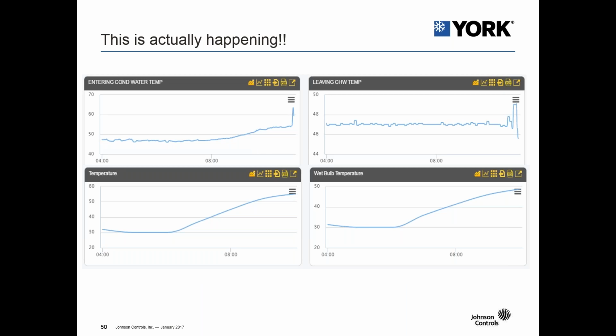So here's just a quick screenshot of our dashboard that we have for connected chiller services, where we're able to monitor chiller performance and chiller operation if the client chooses to request that service. So here's an installation we have at a pharmaceutical research lab in the Northeast region of the United States, and you can see we have entering condenser water temperatures down below 50 degrees. They're hovering right around 40, 48, 45, and the chiller's maintaining about a 47 degrees leaving chilled water set point. So we do have this operating throughout the U.S., and we have customers that are just thrilled about the operational savings.